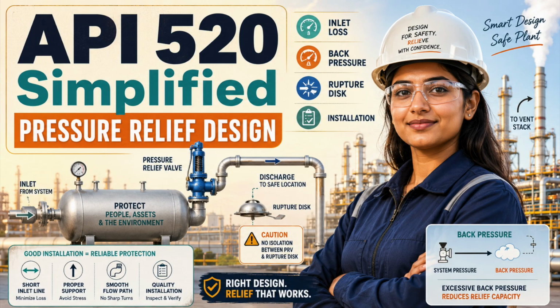If they share the same vulnerable inlet, outlet, isolation arrangement, or operator error path, they may still have a common failure. Redundancy is not equipment count. Redundancy is functional independence. Finally, installation and maintenance access matter. Relief devices must be reachable, removable, inspectable, and protected from damage. Vent connections must remain open and correctly routed.